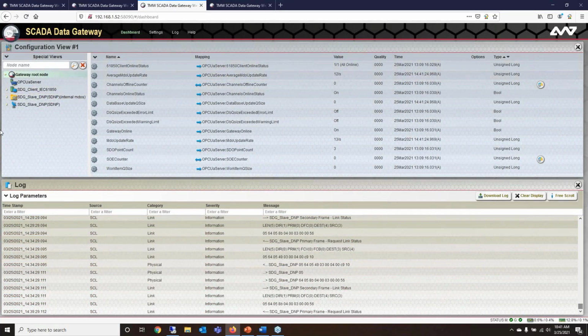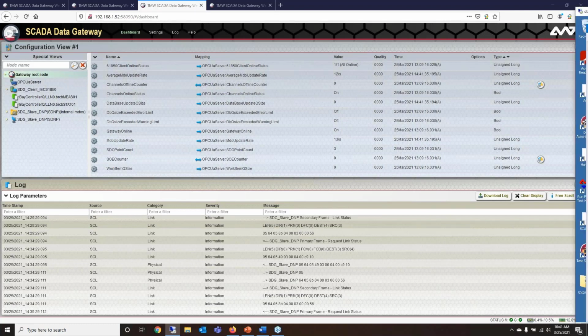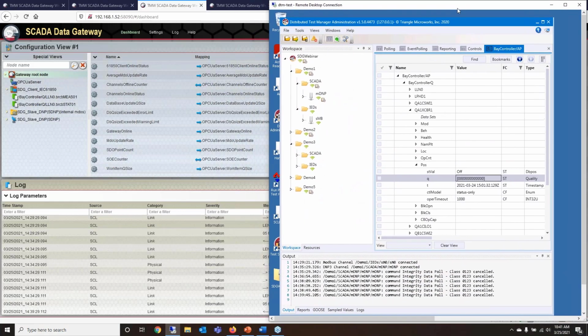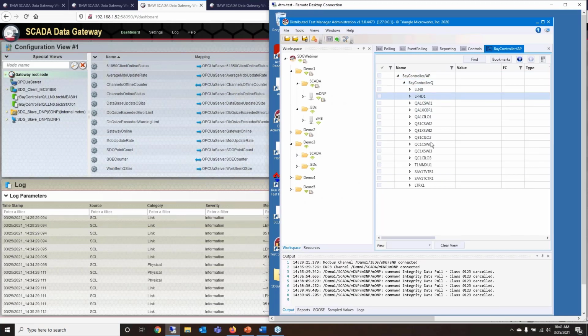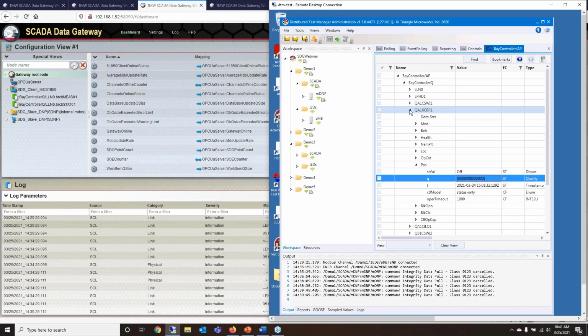So effectively what we have here is 61850, our first model-based protocol that we've been looking at. To show off what that looks like, I'm going to pull up DTM for a second. In this situation, we have a bay controller device, and inside of it, it has several different logical nodes. These are the groupings we were talking about before. If I open up this XCBR, which I know is a breaker, we'll have several different data objects inside of it, but the one we're going to be looking at today is the position object.